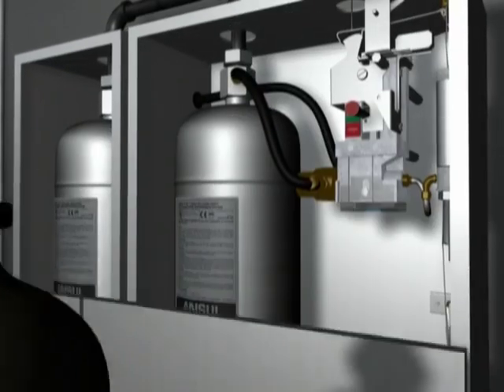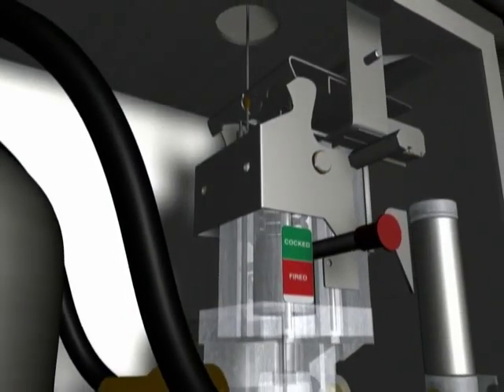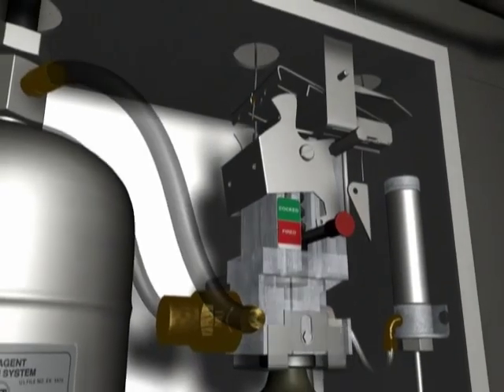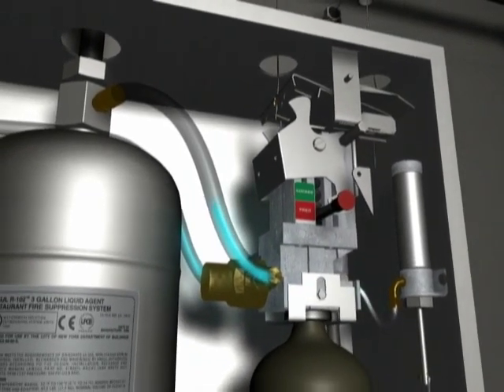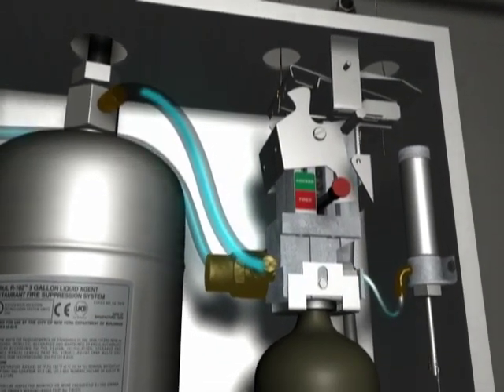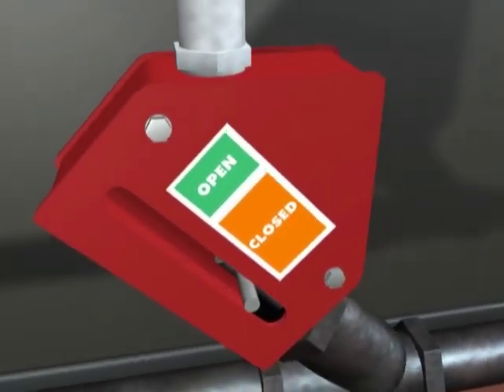This triggers the release of a compressed gas cylinder within the Ansul release mechanism. Simultaneously, the compressed gas pressurizes the Ansulex agent tank and an air cylinder that trips the Ansul mechanical gas shutoff valve.